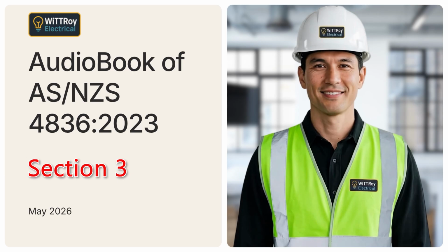Section 3. Isolation, fault finding and testing. Today we're moving into Section 3 of ASNZS 4836. This section is about isolation, fault finding and testing. The main idea is simple. Before anyone works on electrical conductors, electrical equipment or exposed parts, the work must be made safe. That means the equipment must be correctly identified, isolated from all energy sources, secured against being switched back on, tested to prove it is de-energized, and controlled so the safe work area is clear.